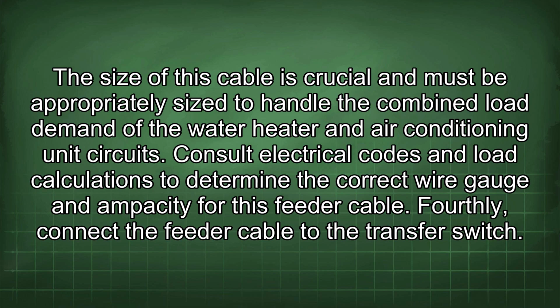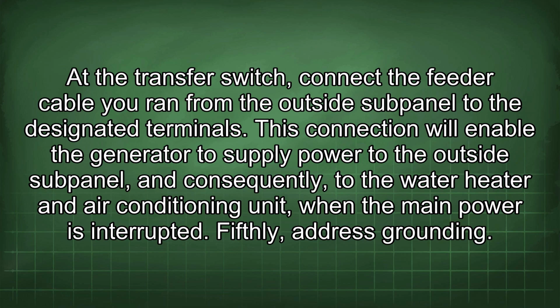Fourthly, connect the feeder cable to the transfer switch. At the transfer switch, connect the feeder cable you ran from the outside subpanel to the designated terminals. This connection will enable the generator to supply power to the outside subpanel and consequently to the water heater and air conditioning unit when the main power is interrupted.